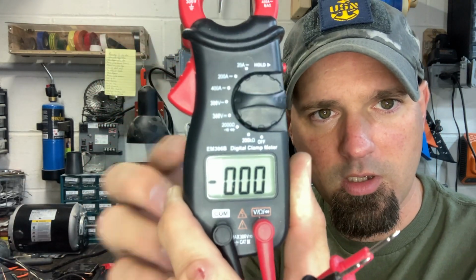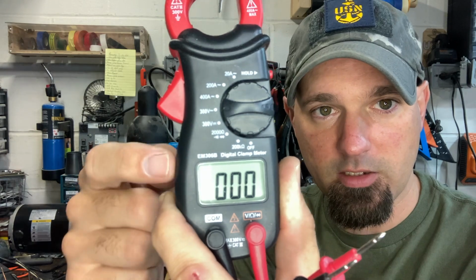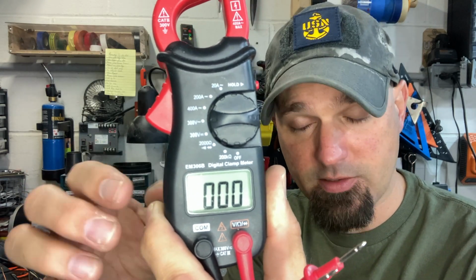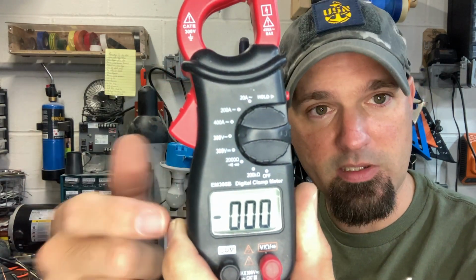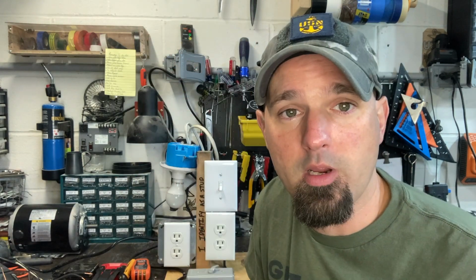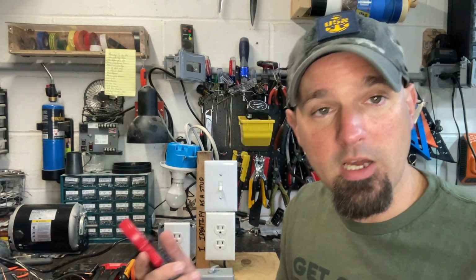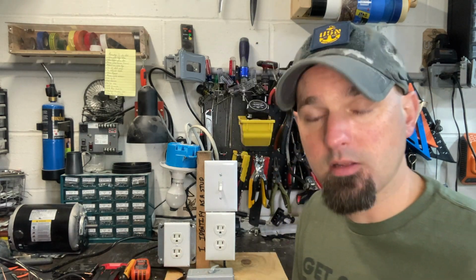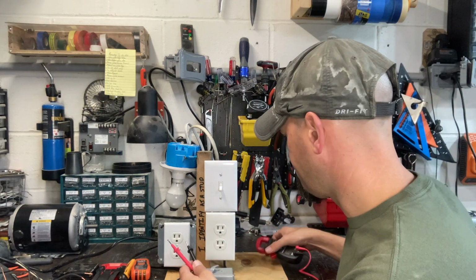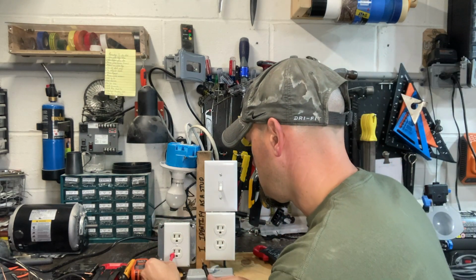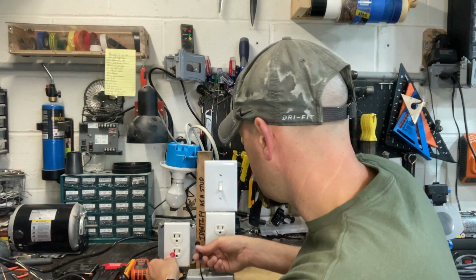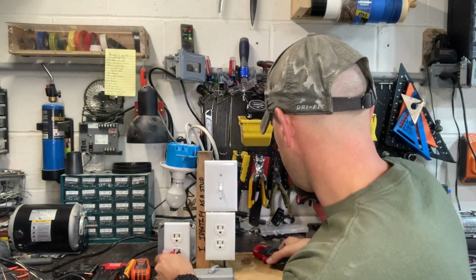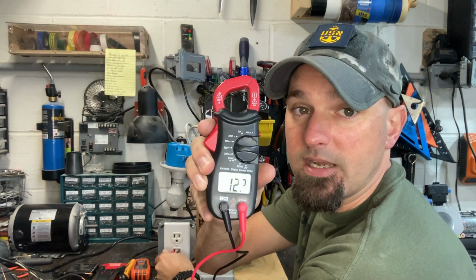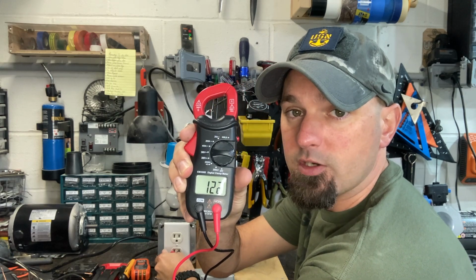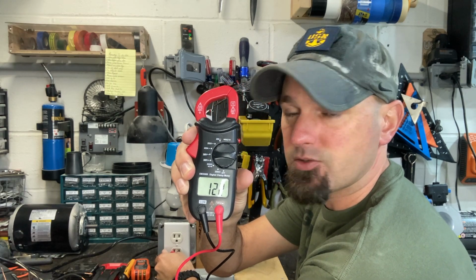And you can see right now it says 0. This is where it's gotten electricians in trouble in the past, because they see that and say, okay, well obviously it's dead, so I'm good. No - it's because your meter's not working properly. So again, live, dead, live. I'm going to take the meter, my two leads, place one on one side, one on the other, and now it's telling me there's 122 volts in that circuit.